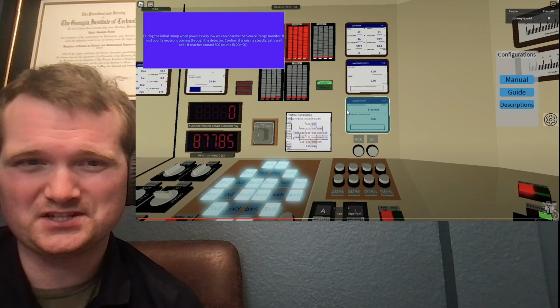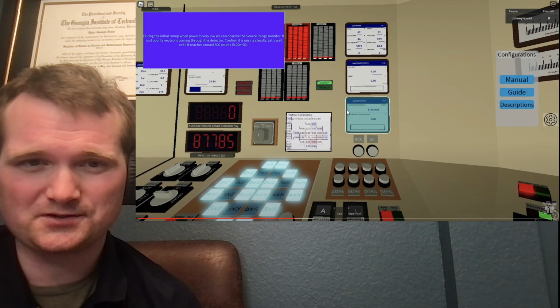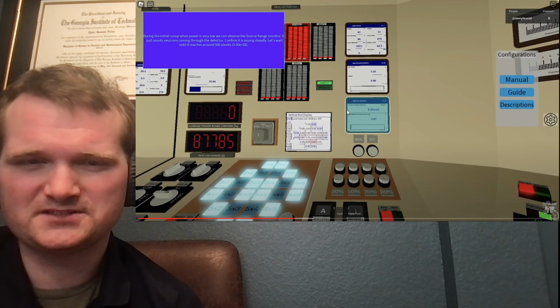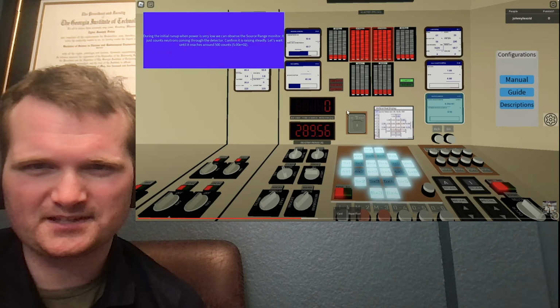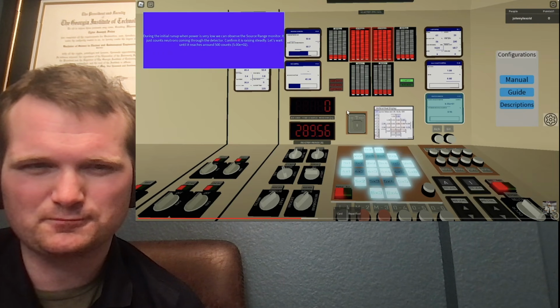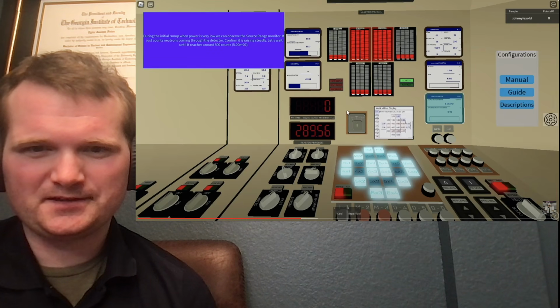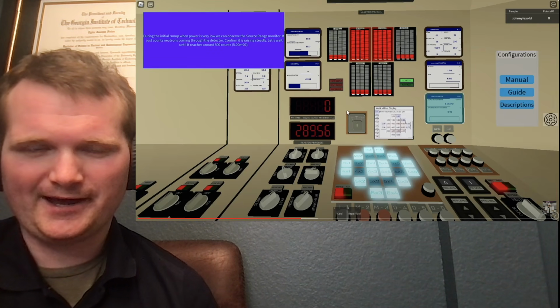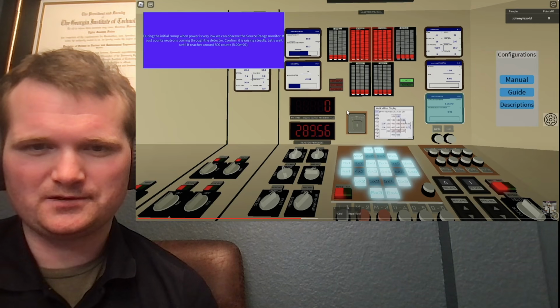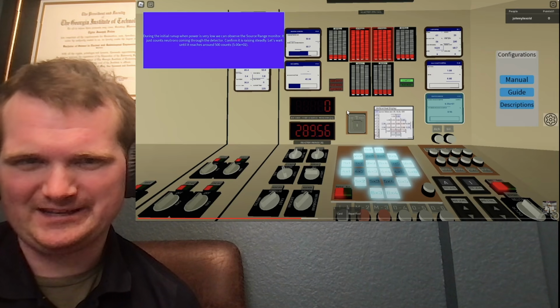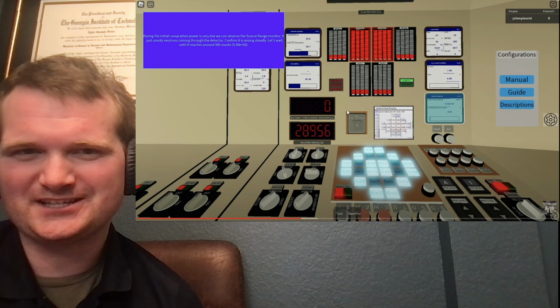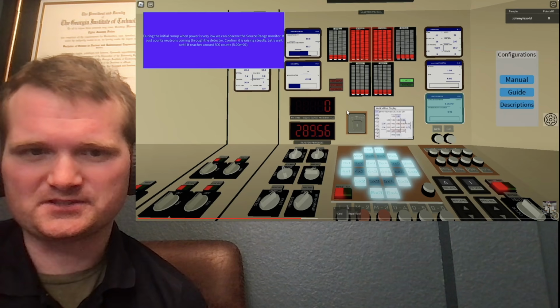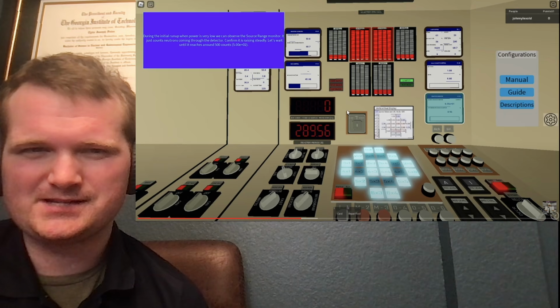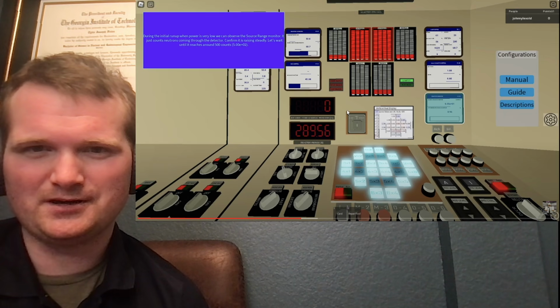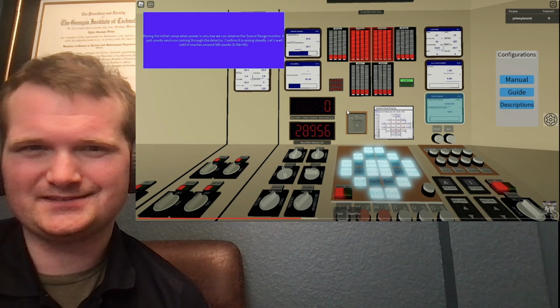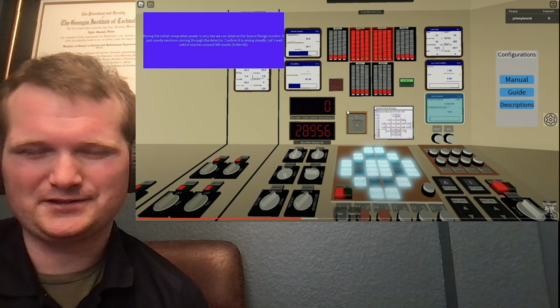There's also reactor engineers, subject matter experts, monitoring all of this. Very, very sacred evolution. The big number you see that's fluctuating right there is reactor period. The reactor period meter is a unit to define how long it takes for the reactor to increase by a factor of e. e being the mathematician's e, that's about 2.7 and some change. So reactor period is a unit of time, typically in seconds. So at this moment, it's going to take 289 seconds for reactor power to increase by a factor of 2.7.